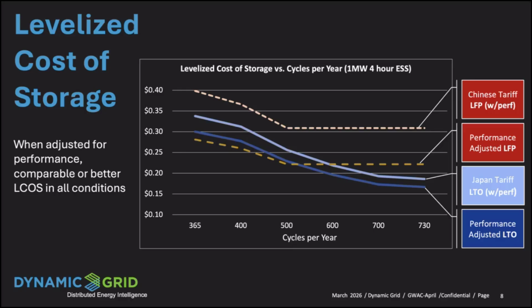We are cost effective with LFP, even though we cost more on CapEx. It's roughly twice on the kilowatt hour basis, though in actual sizing, it ends up being only 20 or 30% more expensive. With the high cycle rates, you end up with a performance adjusted LTO price that is lower than LFP.